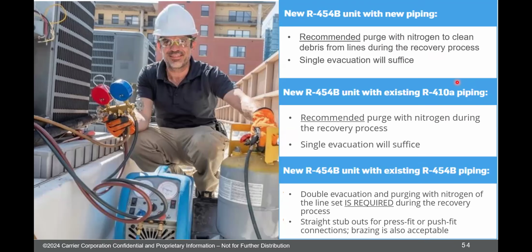If you have an existing R410A piping system and you're going to keep the piping and you're going to convert the equipment over to 454B, you are still only required to purge and evacuate. It's the exact same process. Nothing else is required. You're not needed to do a chemical flush or anything like that.